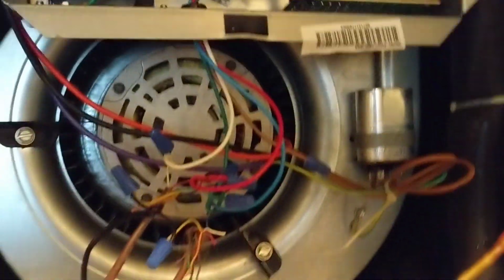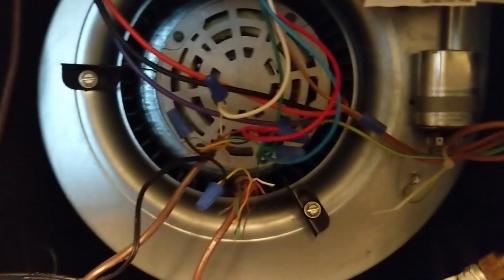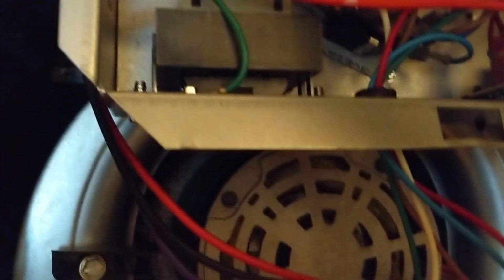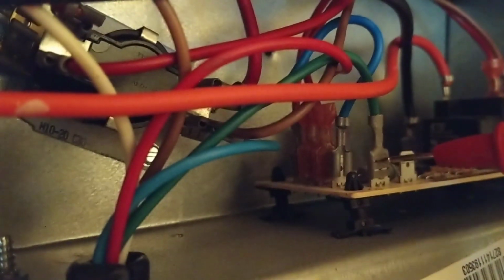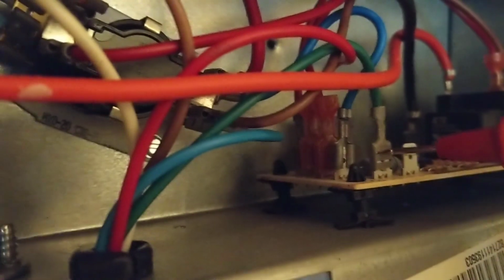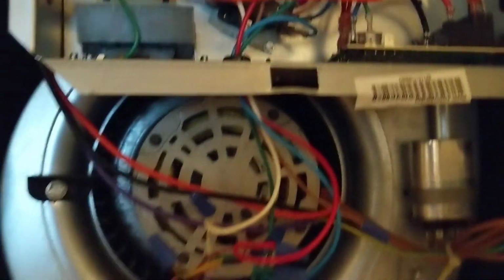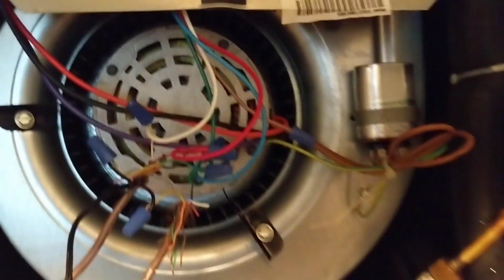Alright, just to confirm, I got the thermostat back on, the fan set to auto, and we will check to see if we're getting 24 volts here. Got one lead on the transformer, one on green. Switch my meter back to volts. And I got 27.5 volts going from the transformer to the green, so I'm definitely getting my 24 volts over. It's just not coming out and starting the fan, so that would lead me to believe the blower board is bad.